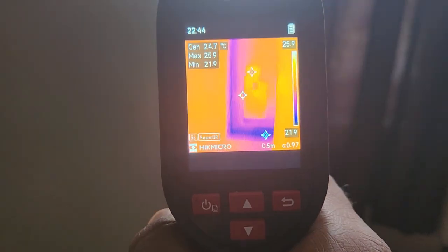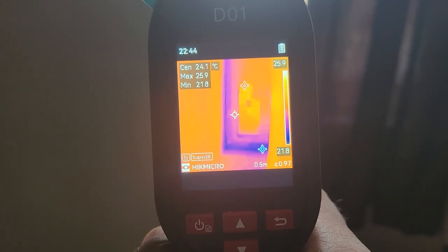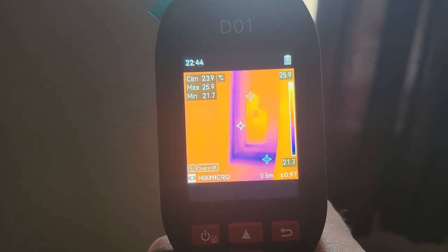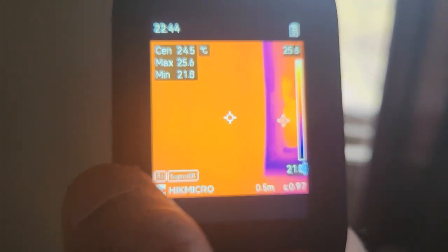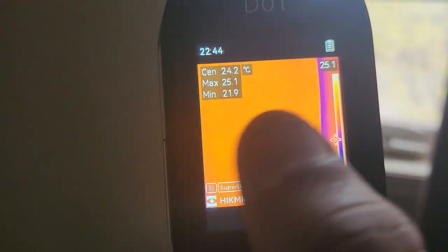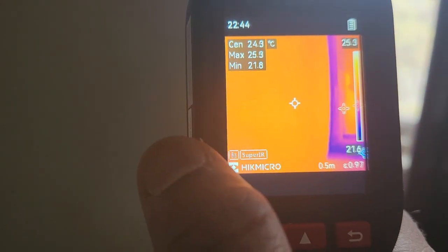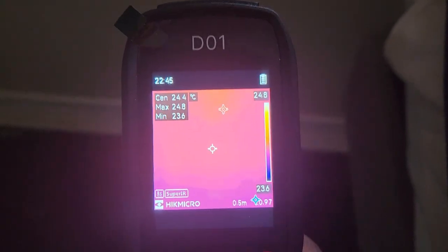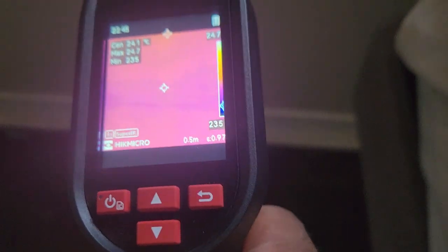So why do you see moisture there? It's not that water is leaking, but yeah, there's a corner, so that means cold layer is seeping through it more than other areas. That's why you see this strip on this side more dark orange. So this shows the color indicator. That means there is no heat loss in this area. The more you see towards the shade at the down, the more heat loss, or you can say insulation issues you have.